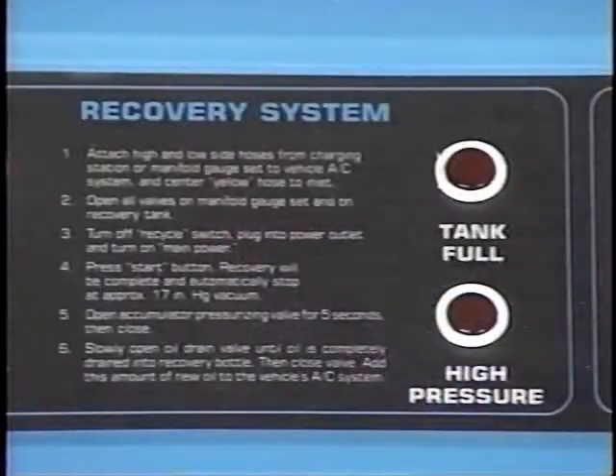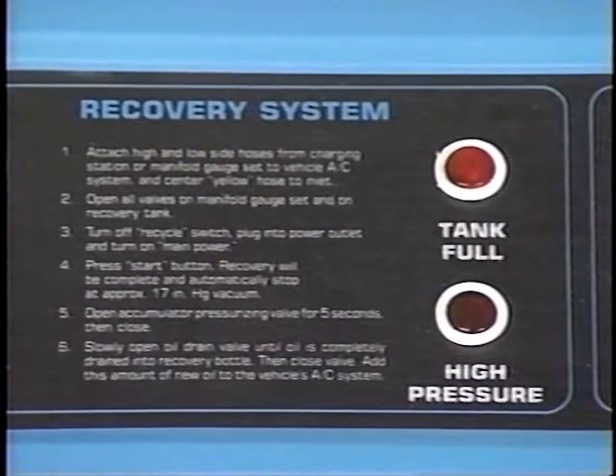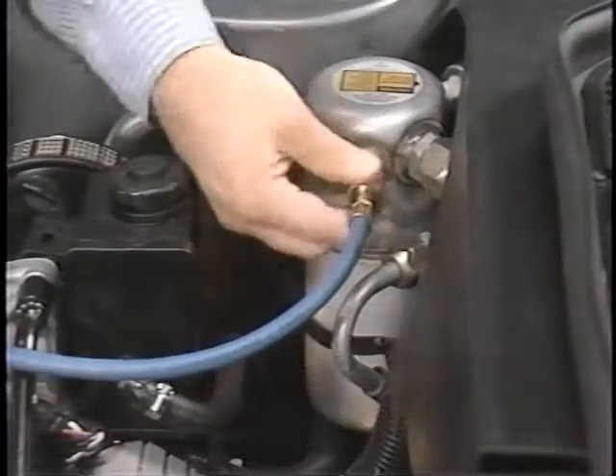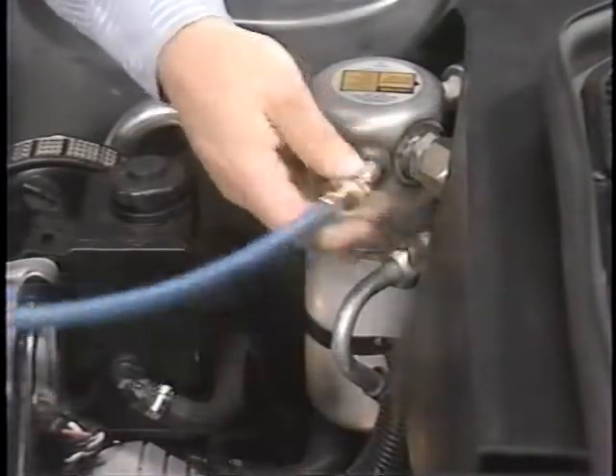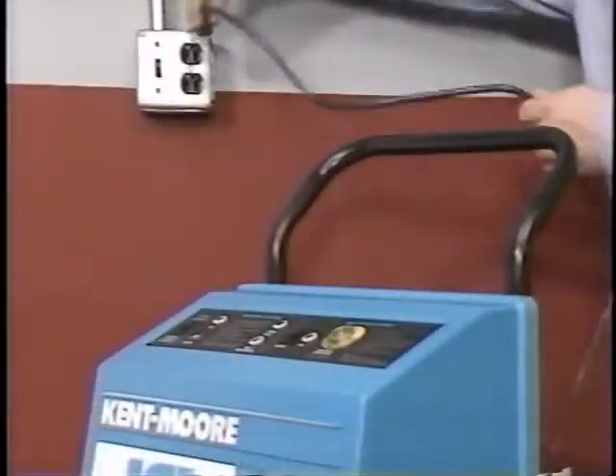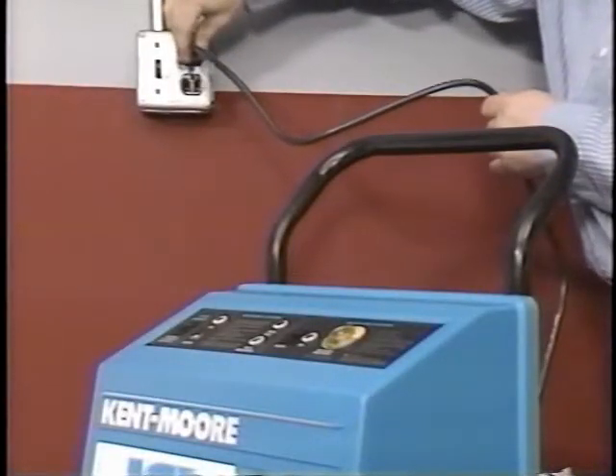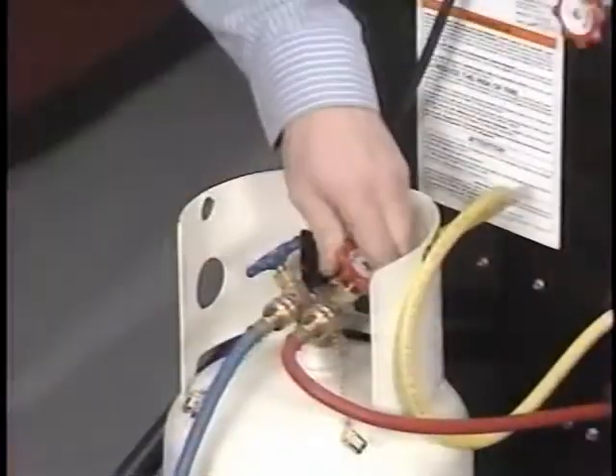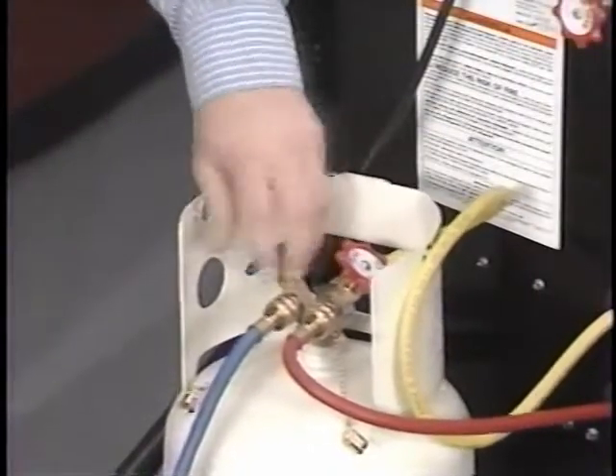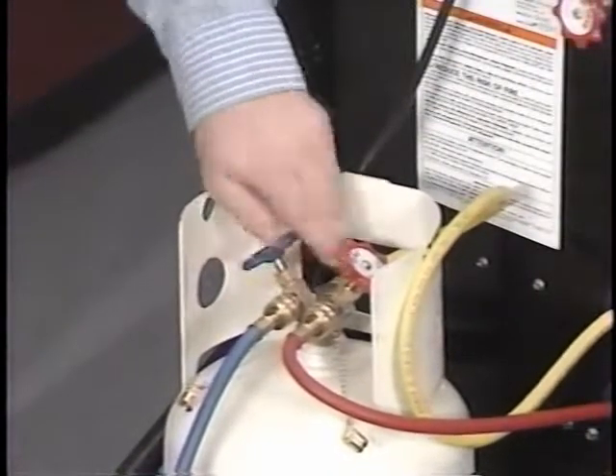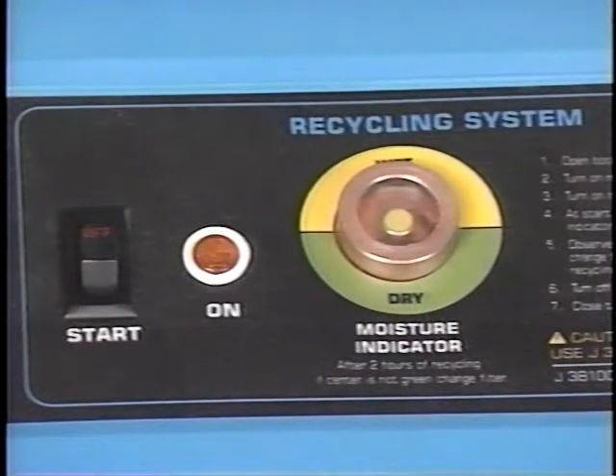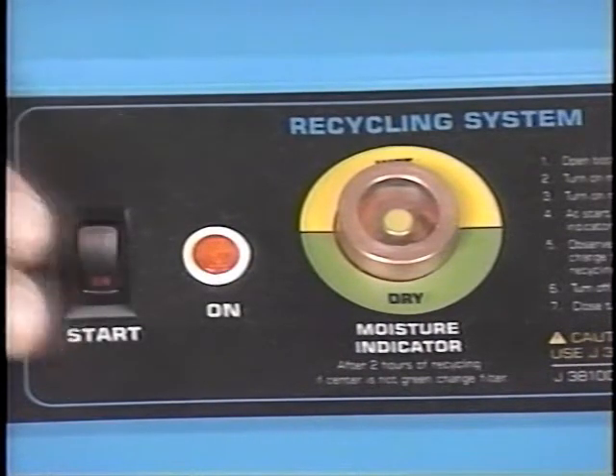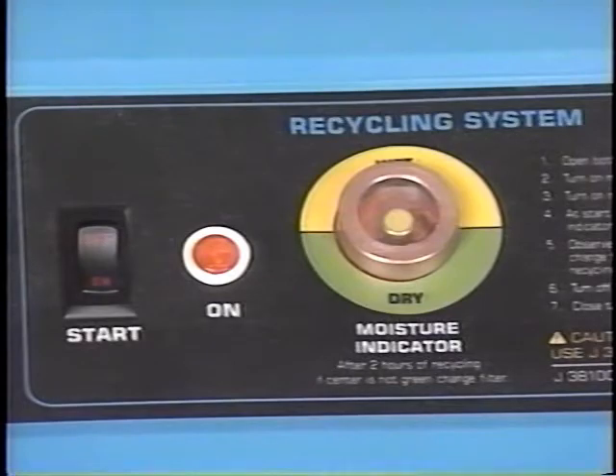When the recovery tank is full, a switch in the weight platform shuts off the system and turns the tank full light on. Disconnect the system from the vehicle for recycling. When you're ready, plug the system into a 110-volt AC outlet. Be sure to open both valves on the refillable storage tank. Push the recycle start switch. The recycle on light indicates that the system is working.